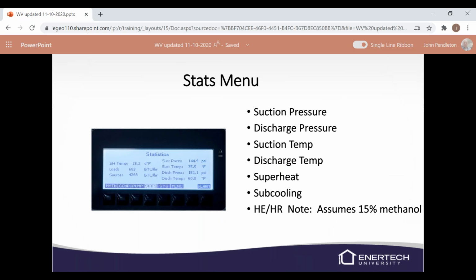Stats menu, here it will show you your superheat, your load BTUs, your source BTUs, the suction pressure, suction temperature, discharge pressure, and discharge temperature. It will show your heat of extraction or rejection, but it will assume that you're using 15% methanol. So if you were to calculate it by hand, your calculation could be a little bit different than what's actually on the screen here, but it should be fairly close.